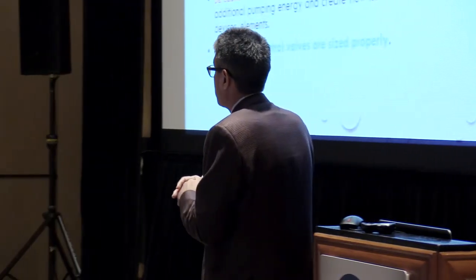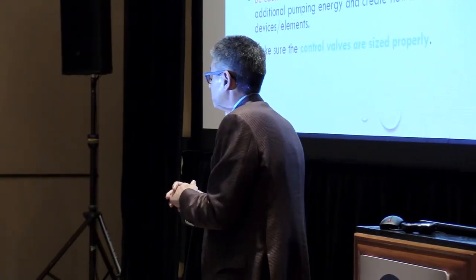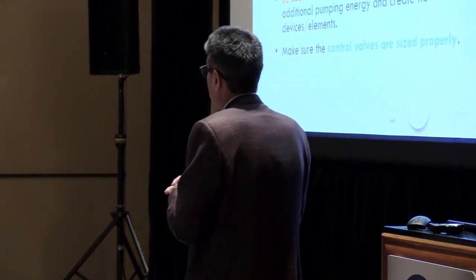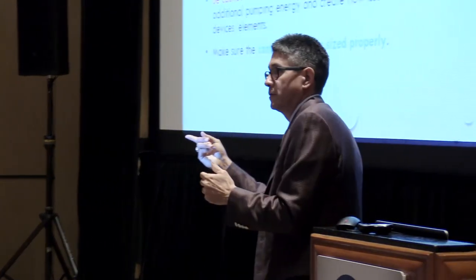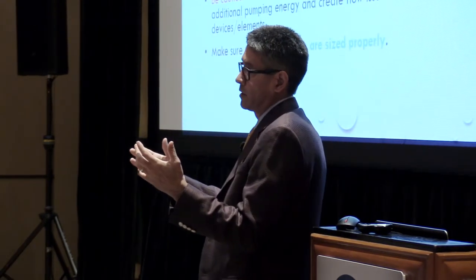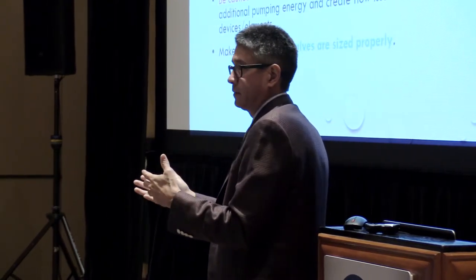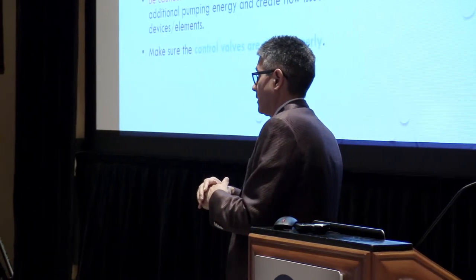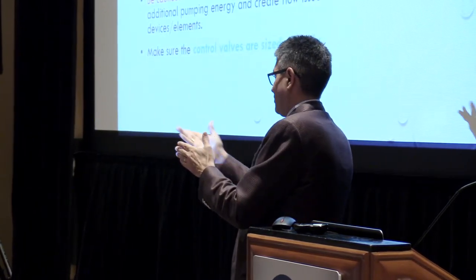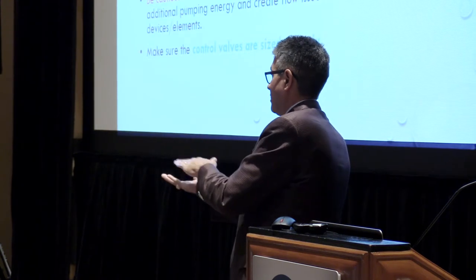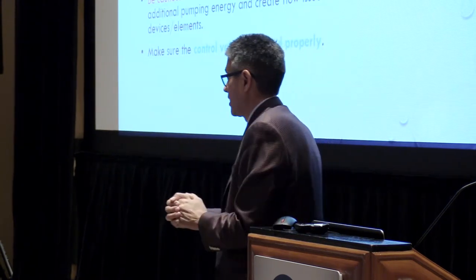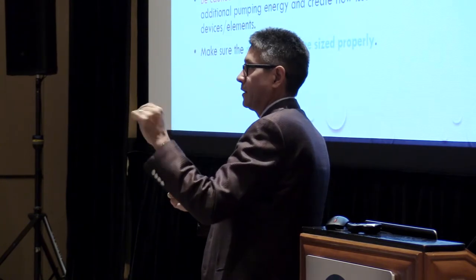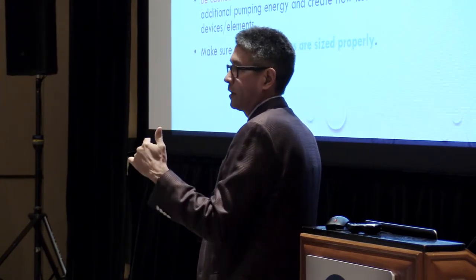Yes? Do you have any concerns with the auto flow limiting devices fighting the control valve? Yes. So the question was, do you have a problem with autoflows fighting a control valve? It goes back to the sizing and getting the control valve sized correctly. And then what ends up happening, you probably get a control valve hunting some, and then you get a chatter sometimes.